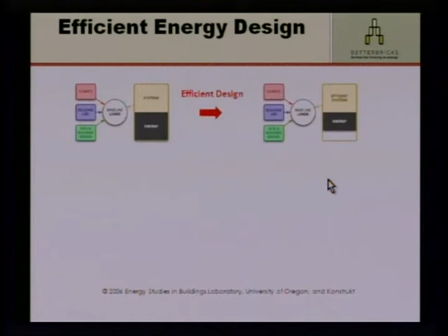So here's how you do it with integrated design - this is why you need your engineer involved not at the 95% design stage, but at the 5% design stage. The first thing you do is get rid of as many loads as you can, through orientation, selection of glazing, and lining things up so you have airflows, reducing those loads. You choose smart lighting so you're not wasting energy cooling for lights you didn't need. So first you make small loads. Small loads require smaller systems, so you get savings because the system is smaller and the energy it uses is smaller.